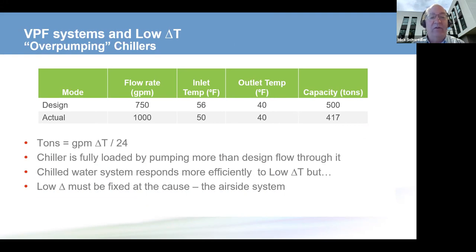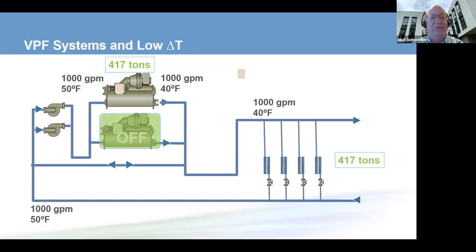So instead of turning another chiller on, we simply allow the pumps to keep ramping up. We pump more water through that evaporator, and we are able to fully load that chiller, even though it's only getting a 10 degree delta T. So this allows a variable primary flow system to respond to low delta T issues, but it doesn't fix them. They can only be fixed out at the air side, out of the coils. So we would prefer, and I suggest we should, fix the problem, cure the disease instead of treating the symptom.